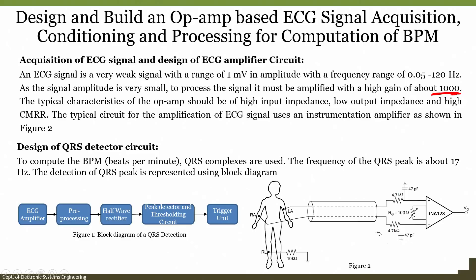For QRS detection, we have the ECG amplifier followed by pre-processing, then a half-wave rectifier, peak detector and finally the trigger unit. These are the steps in QRS detection. To compute beats per minute, QRS complexes are used. The frequency of QRS is about 17 hertz. The detection of QRS is represented using that block diagram we have just discussed.